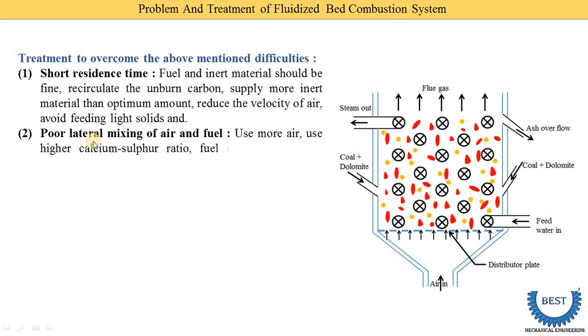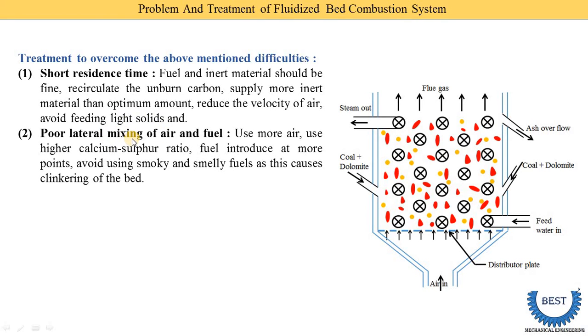The second problem is poor lateral mixing of air and fuel. To avoid poor mixing: first, use more air — a higher mass of air is required. Second, use a higher calcium-to-sulphur ratio, as calcium and sulphur are types of inert material like dolomite. Third, introduce fuel at more points — instead of two entry points, we can use three or four points so that the fuel and inert materials are properly mixed.